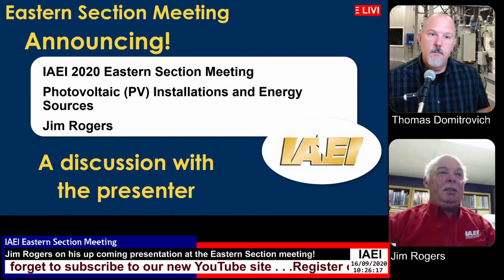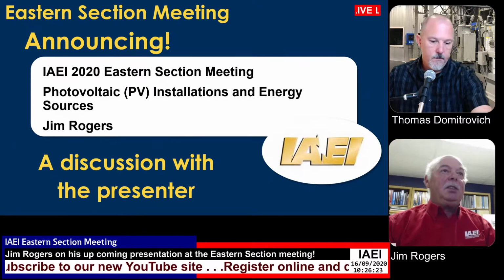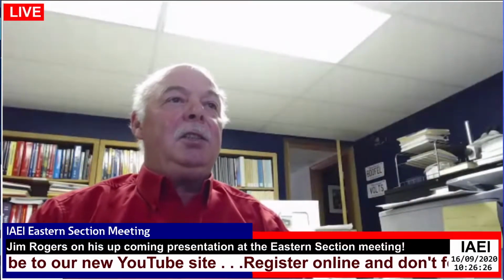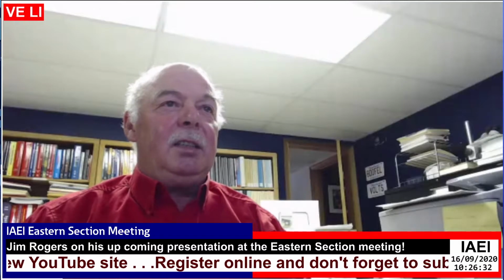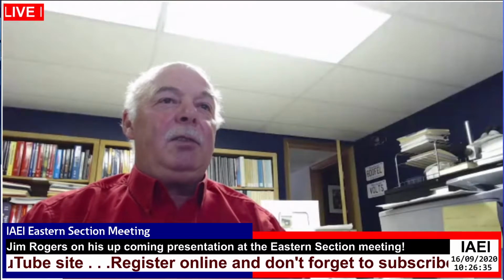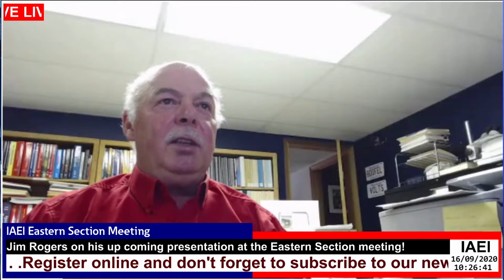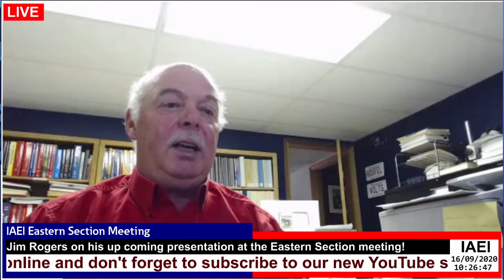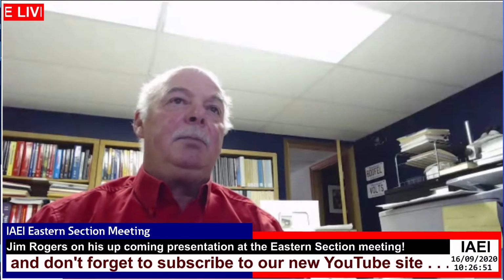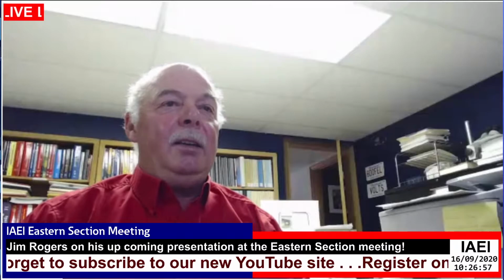Because CMP4 deals with these issues, I'm going to be discussing PV installations and energy storage. Energy storage is becoming very, very important all across the country, and it's helping with things that I'm not going to get into right now. Utility grids have to worry about things such as solar saturation. What that means is if you have too much PV entering the utility grid, and for some reason it goes dark because a cloud comes over or whatever, and a lot of the PV drops out, the utility company has to be able to bridge the gap. Energy storage is one of the ways that they can do that. So it's becoming more and more important.